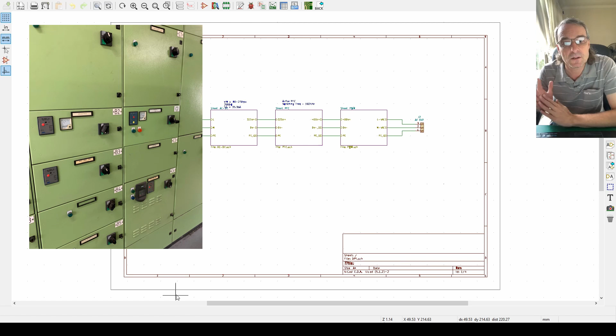So this product that this colleague wanted me to make is known as a dip-proof inverter. Now, what we have is motor control centers - think of it as a big cupboard full of motor circuits with the protection that controls the motors. So you would tell this thing to start, the protection relay will pull in a contactor, the motor will run, and the protection relay will look after everything, and if there's a fault, it will drop the contactor.